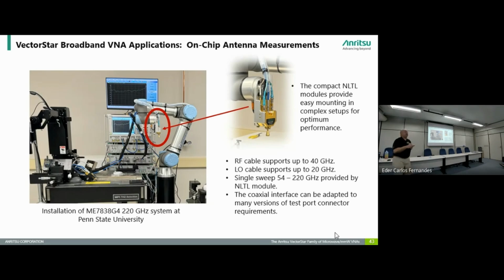If you want the proper gain of the antenna, then you need to do a power calibration followed by a receiver calibration. It's what I talked about earlier, because now instead of doing relative measurements, you would be wanting an absolute measurement. And for that, you need a calibrated receiver. The only way you can calibrate a receiver is to have a calibrated source first and use that source to calibrate the receiver. Now you can measure the gain, but it needs an absolute measurement.